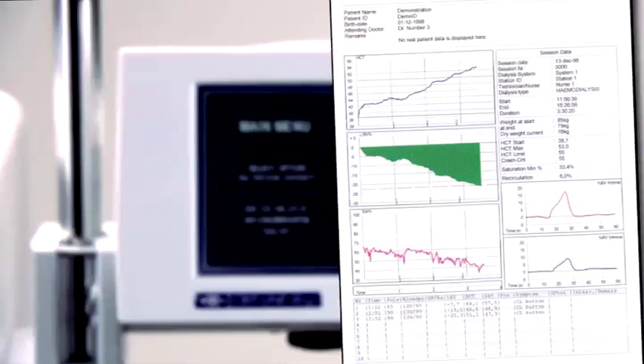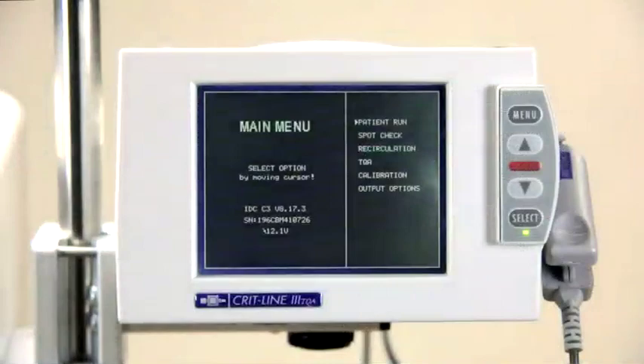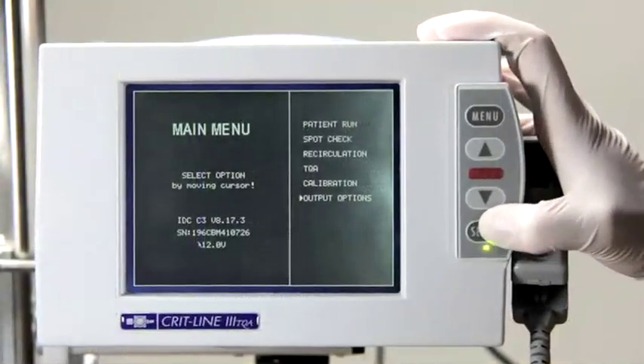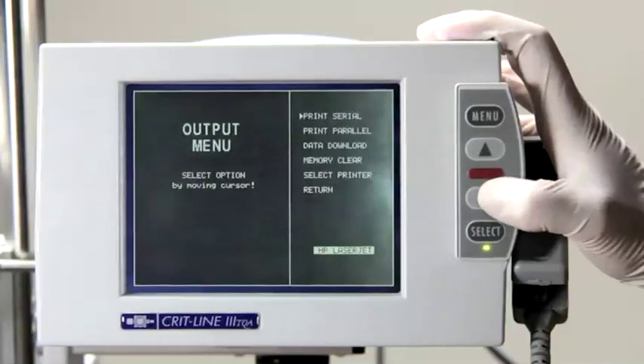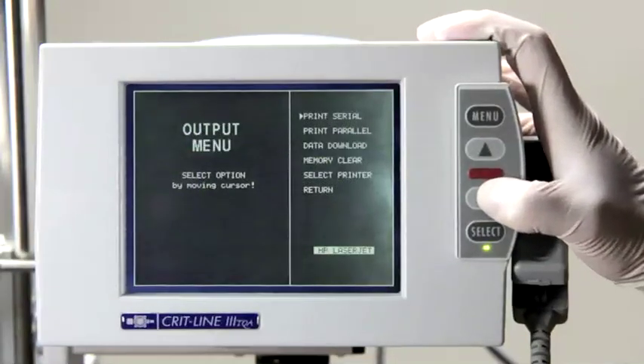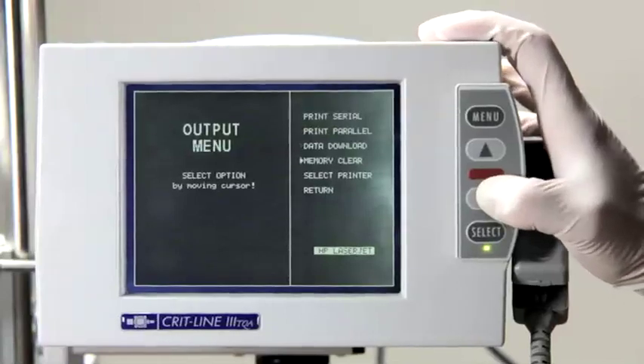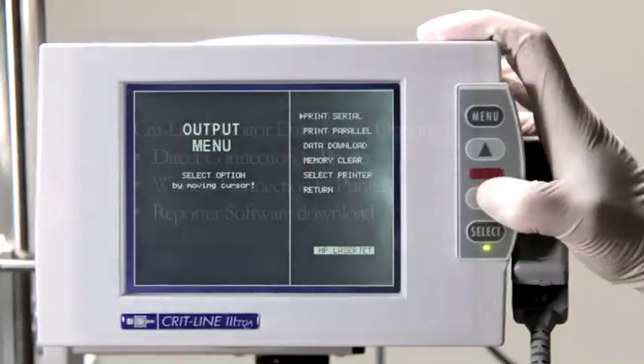The header information also includes the serial number and software version of the Crit-Line monitor, along with the original calibration date and last verification date. From the Output menu, you can select how you want to print this treatment profile, as well as choose your printer. To choose a printer, move the cursor to Select Printer and press the Select button. There are 3 ways to get printouts and/or data of the treatment profiles: direct connection to a printer, wireless connection to a printer, and via our reporter software.